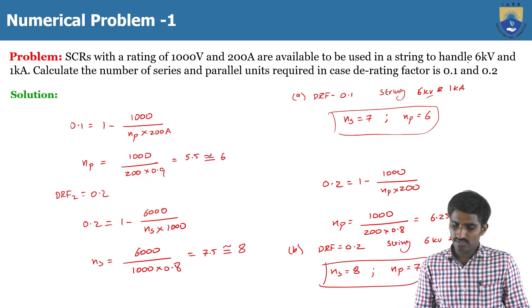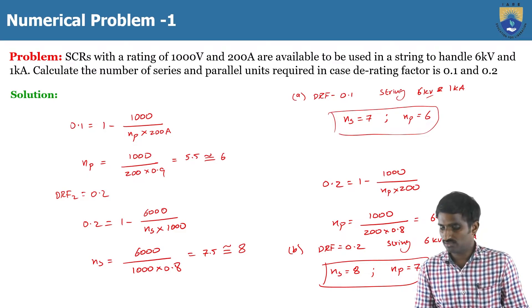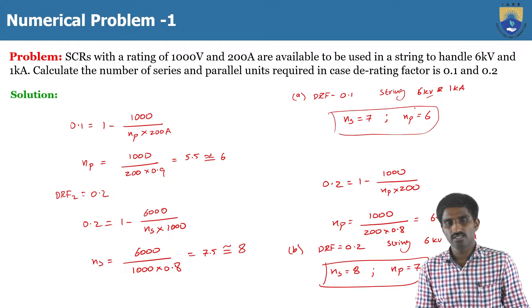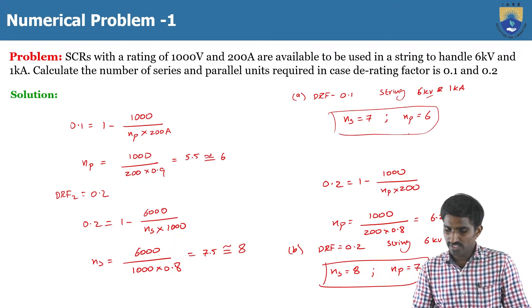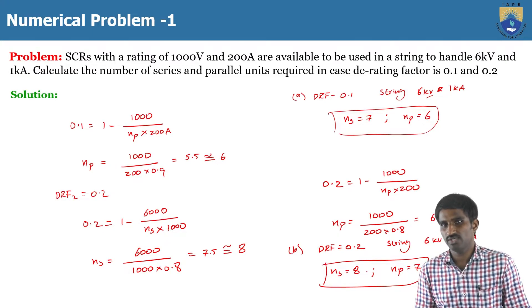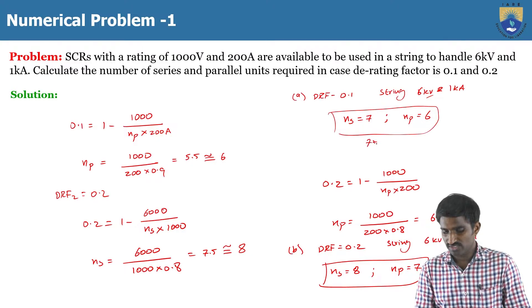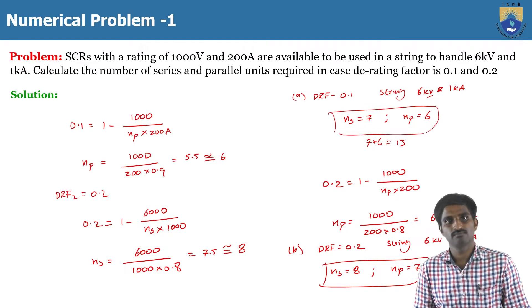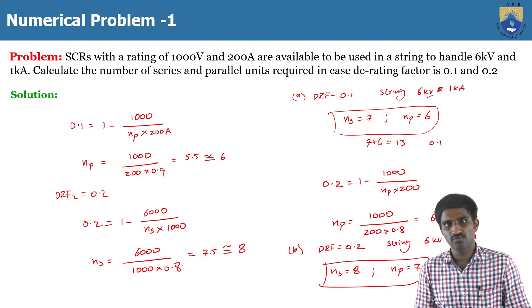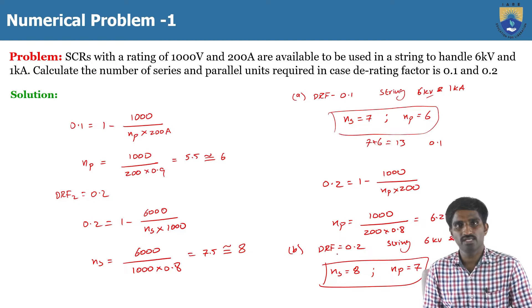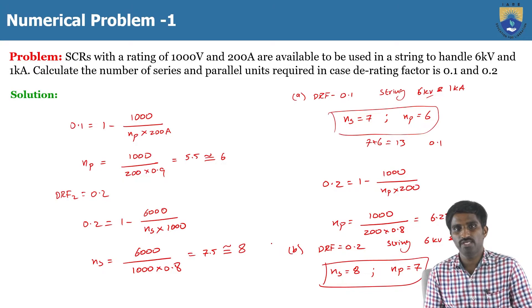Comparing the two cases: for the same string rating but different derating factors, the required number of thyristors changes. For DRF = 0.1, total thyristors = 7 + 6 = 13. For DRF = 0.2, total thyristors = 8 + 7 = 15. When increasing the derating factor, the number of thyristors required in a particular string also increases.